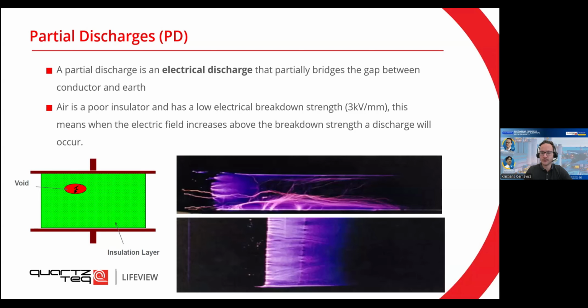First of all, it's an electrical discharge, a partial discharge between a conductor and earth. If you imagine that one of the plates here is a conductor and the other plate is the earth, the insulation should prevent any charge going through. However, if the insulation has a gap, so in the red there is a void, instead of insulation there is, for example, an air gap. Through this air gap you can have a discharge once a particularly high voltage between the plates has been reached. To give you an idea, the high voltage we're talking about is around 3 kV per millimeter. So if your machine is rated at 6 kV, gaps as small as half a millimeter can already give you partial discharges. And when these discharges happen, they can often increase this gap because more deterioration of the insulation layer will happen.